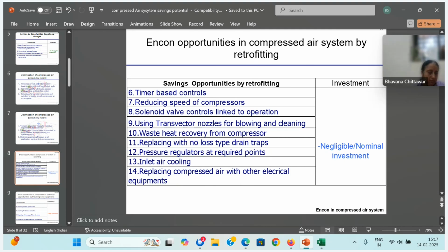Your capacity will enhance actually. For example, in cleaning applications, certainly you can go for transvector nozzles. You can cut down your consumption by more than 60 or 70%, by using transvector nozzles. Then waste heat recovery from the compressor. There's a tremendous amount of heat available in the compressor. In an air compressor, almost more than 90% of the energy is spent as heat. It is dissipated as heat. So this heat can be converted into useful energy wherever your plant requires.